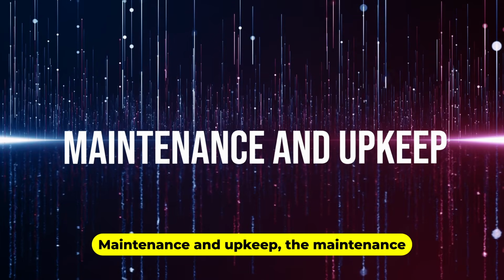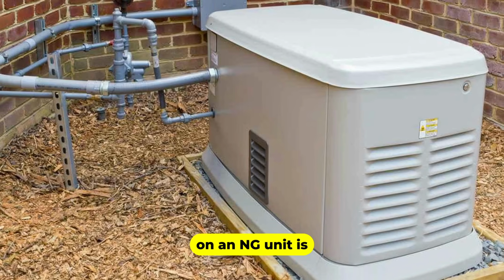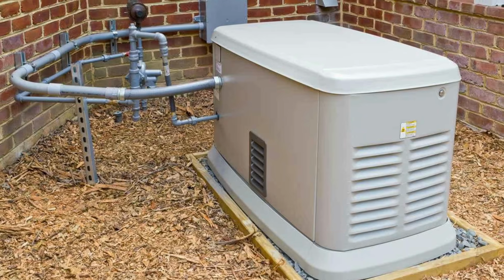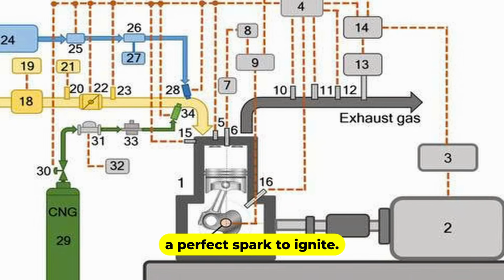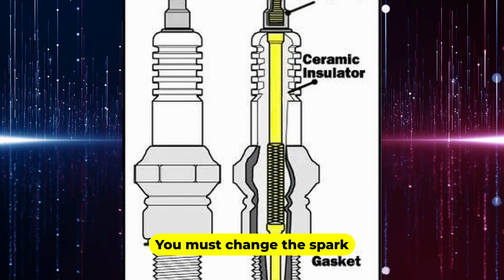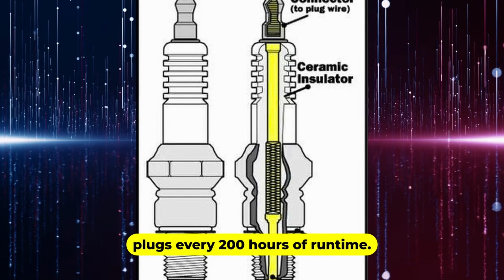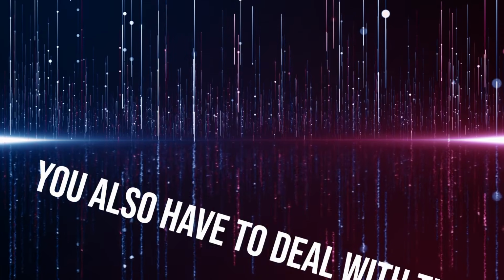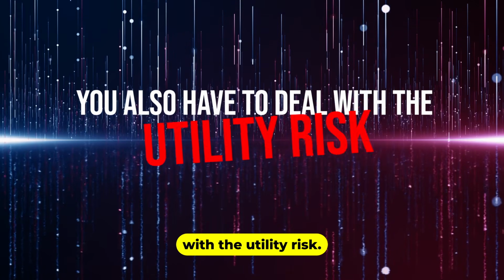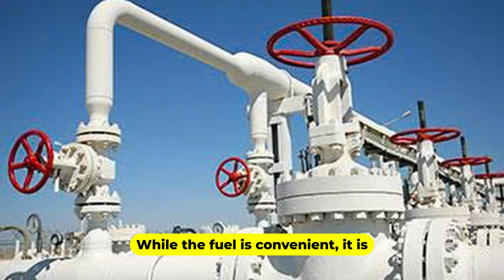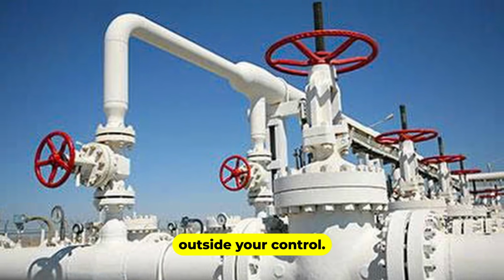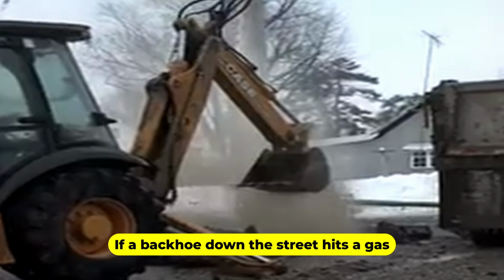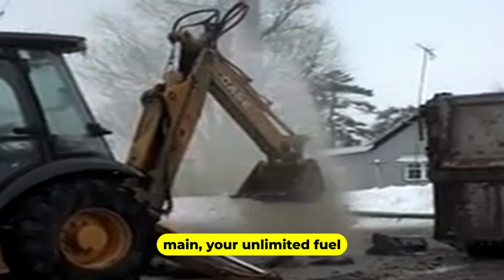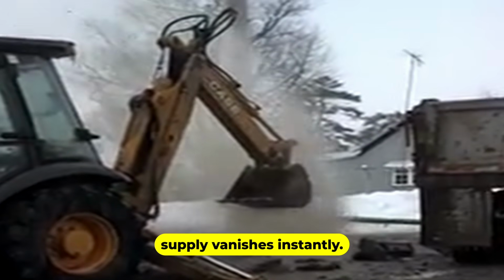Maintenance and upkeep. The maintenance on an NG unit is centered on the spark system. Because the fuel relies on a perfect spark to ignite, you must change the spark plugs every 200 hours of runtime. You also have to deal with the utility risk. While the fuel is convenient, it is outside your control. If a backhoe down the street hits a gas main, your unlimited fuel supply vanishes instantly.